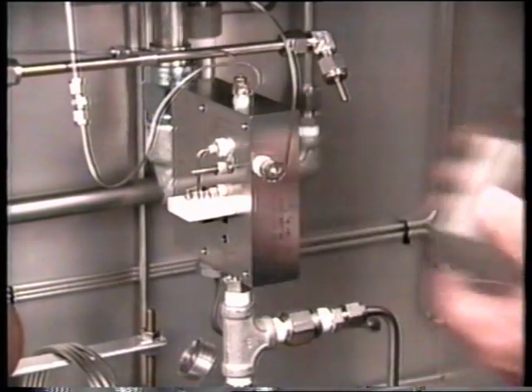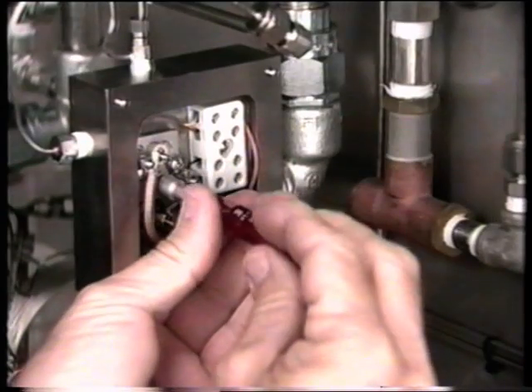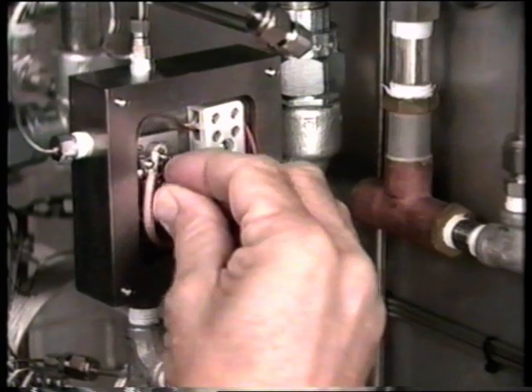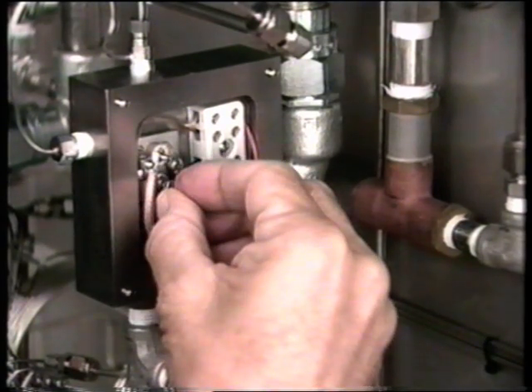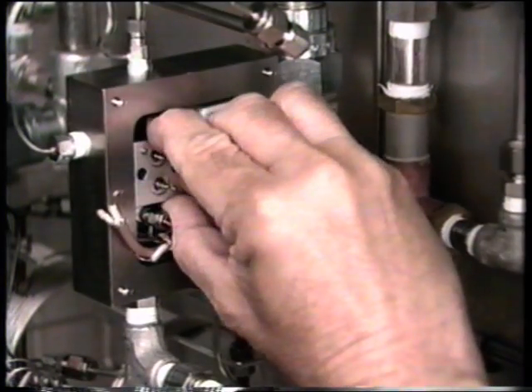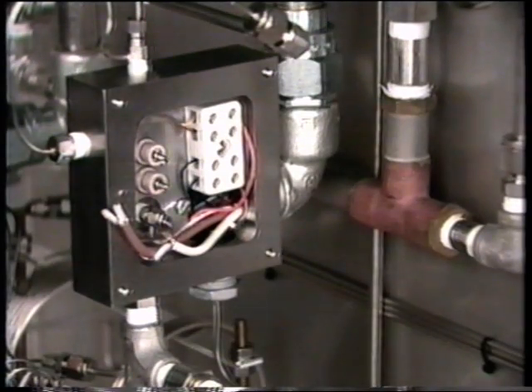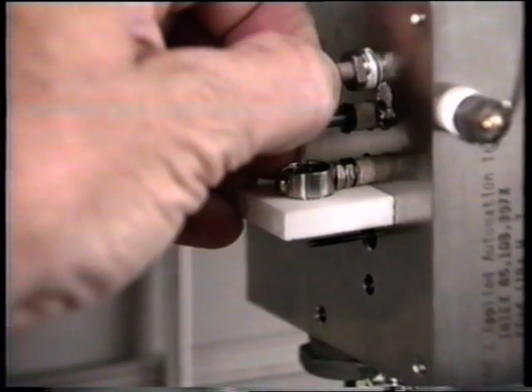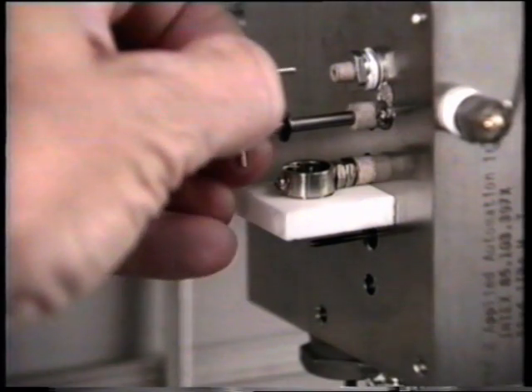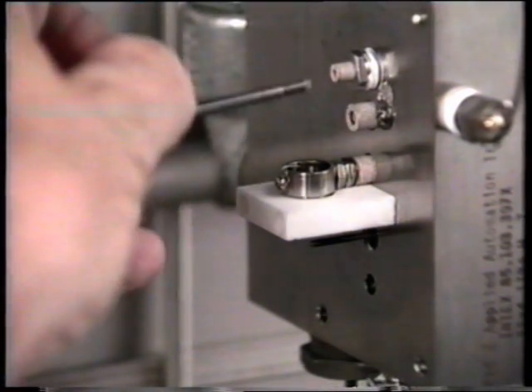Remove the terminal cover and the sensor cover. Remove the bias ignite and signal cables from their electrodes and ground clamps. Remove all nuts and washers. Remove all ground clamps and lift off the insulator plate. Loosen and pull out the burner clamp nut and the bias ignite electrode.